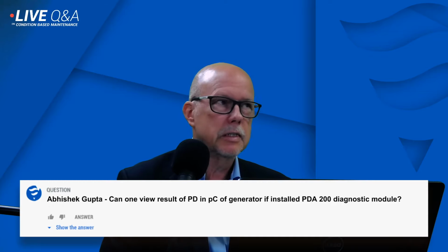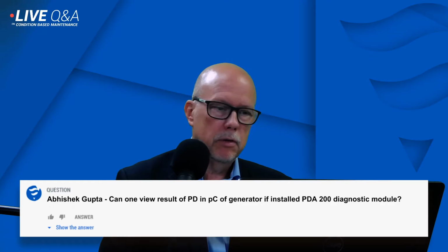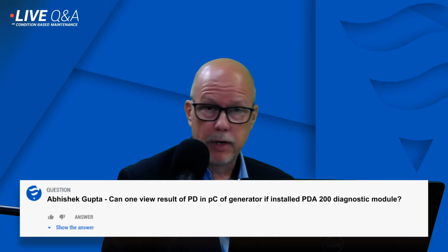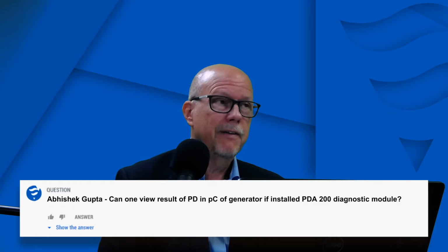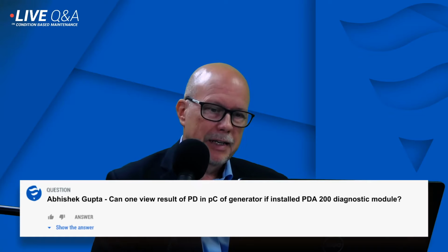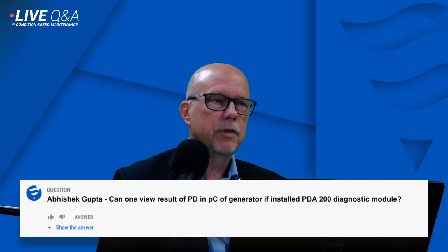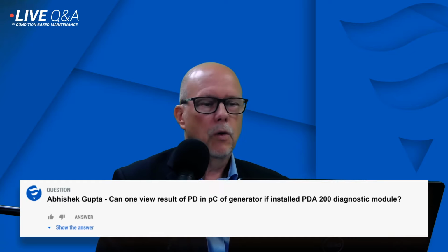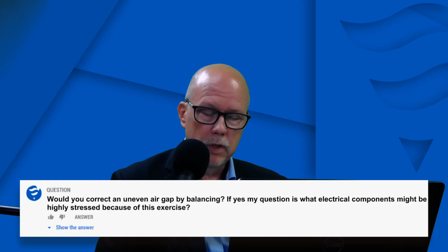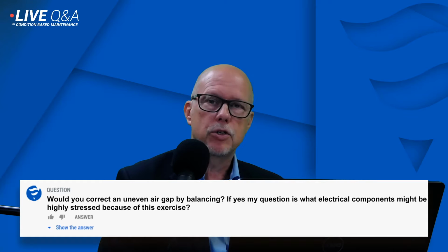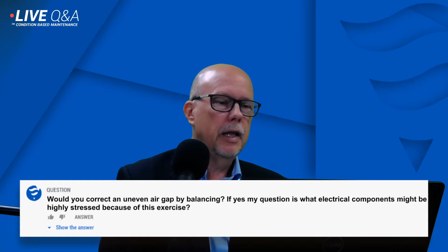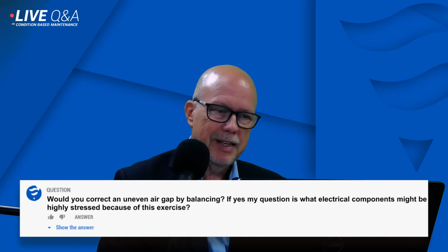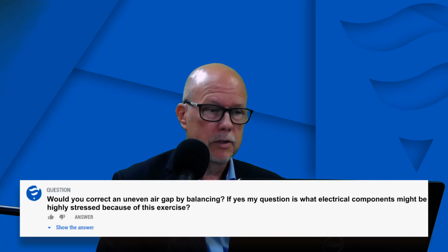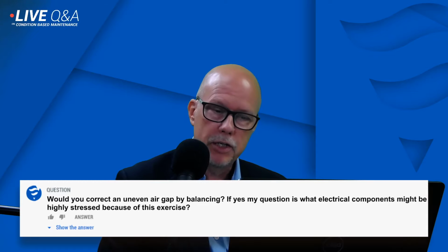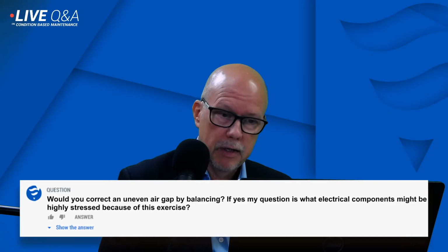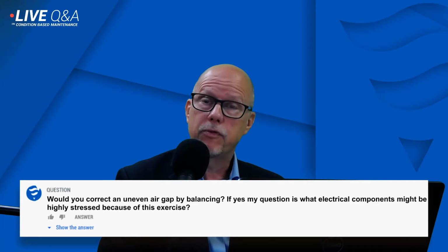undetected. And the reason for that is that if you look only at the vibration panel, if you have excessive vibration at speed no load before excitation, which is quite often the case, when you apply the field, as I mentioned, it becomes magnetically coupled, and you should see the vibration decrease. But if the air gap is uneven, what happens is when you apply the field, the rotor will tilt towards where the air gap is smallest prior to the excitation. And what happens there is that the coupling becomes so intense that the vibration decreases significantly. So if you're only looking at the peak vibration, you will see the vibration decrease significantly, leading you to believe that the unit is performing very well.